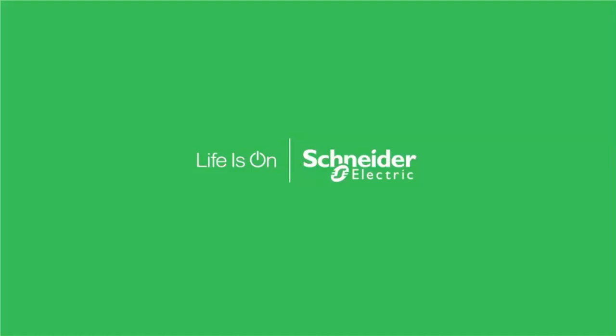Great. Are all mitigation solutions effective for either parallel or series arc flashes? If not, which are applicable for each? Okay. Now, parallel and series, I think we'll get more into the low voltage, almost residential kind of things. The arc fault circuit breakers that are applied in residential, and there are different algorithms that they may use for parallel or series arcs.